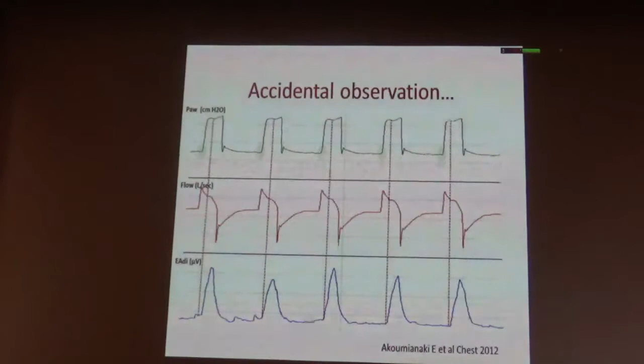But when we measure the electrical activity of the diaphragm, our surprise was to see that at every breath, there was a diaphragmatic contraction starting approximately in the middle of the breath. So the patient was not triggering the ventilator. And again, when we change the rate on the ventilator, the rate of the diaphragmatic contraction had exactly the same change. But it was triggered by the mechanical insufflation, again by a mechanism which we don't know. And you see, it's very difficult to detect, because the only way would be to say, well, maybe there is some curvature on the pressure curve, but again, this is very difficult to detect.